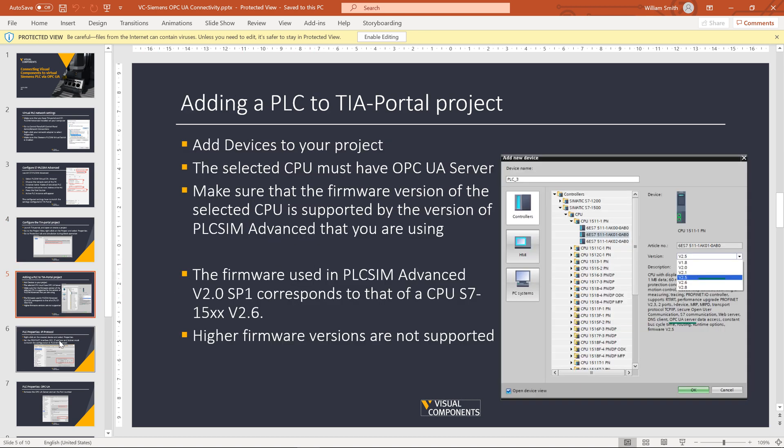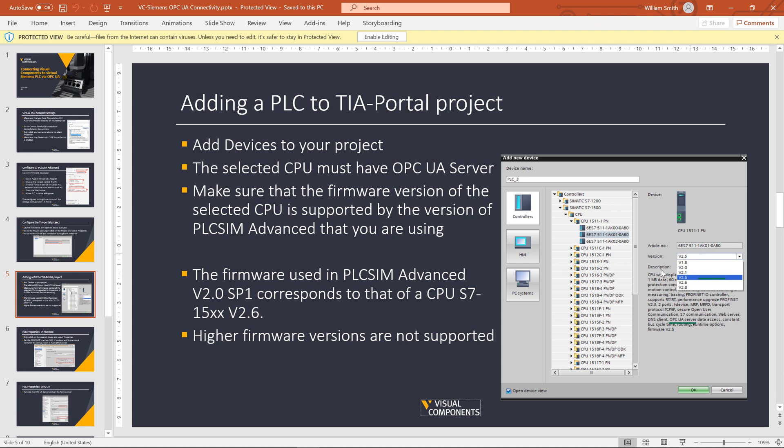Select the PLC that can support OPC UA. It should provide you a description here if it can or cannot. In your case, if you're directly connecting your own PLC, like a 1200 or 1500, make sure you do have the firmware updated so it can support OPC UA communication.